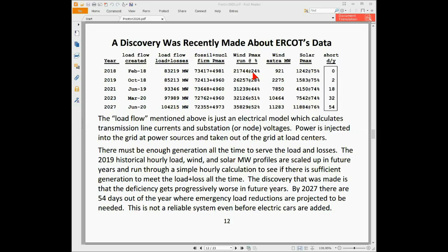Then there's some wind that's not quite on the coast but close to it, which they may run up to 50% in the load flow case. The rest of the wind, very distant from the coast, should be at 14.2%—it was decided in 2013 that non-coastal wind should be run at 14.2%. But if you look in the load flow, you find they're running that non-coastal wind a bit higher than 14.2%, and the amount above that is 921 megawatts.